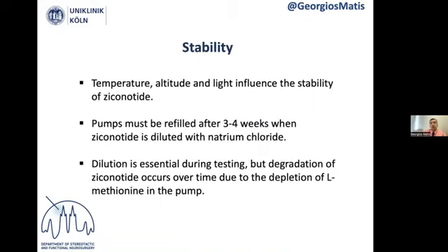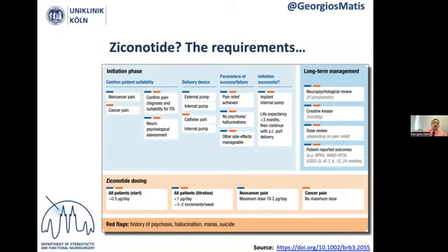Some issues: we know that the temperature, the altitude, and the light influence the stability of the drug. This is why the pumps must be refilled every 3 to 4 weeks when the drug is diluted with sodium chloride. Dilution is essential during the testing, but degradation of ziconotide occurs over time due to the depletion of L-methionine in the pump. This graphic comes from the article that I showed you, which was published in Brain.